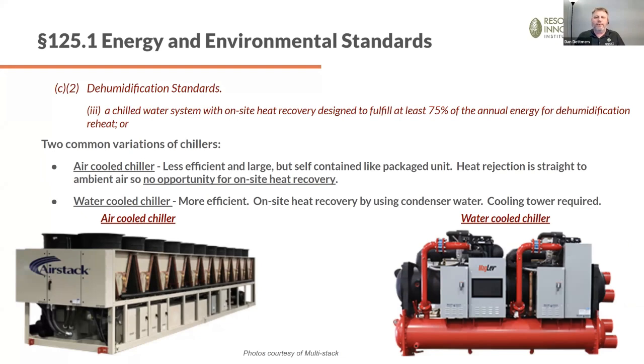Here we have two different types of chillers. On the left is an air-cooled chiller, on the right is a water-cooled chiller. What's the difference? The air-cooled chiller rejects its heat to ambient air, so away it goes - that's how we get rid of the heat in order to cool off the water that's going to cool your space. That means there is no opportunity for on-site heat recovery from that unit. That means I've got to get on-site heat recovery from something else, from another room, from solar, from recovering heat from some process, maybe your extraction facility. It makes it a little more difficult.